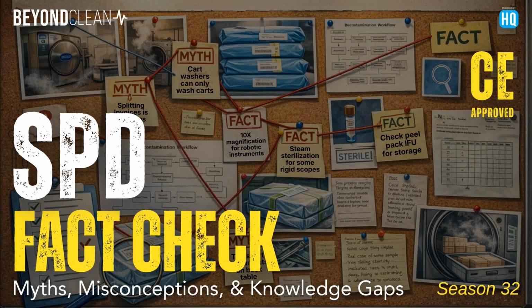From a manufacturing or design standpoint, we're concerned with how quickly we've ramped that temperature up and how quickly we've ramped it down. Let me give you an example: a conventional oven. When we turn it on to heat up, it slowly ramps up to temperature, exposes whatever we're cooking for a chosen period, and then slowly cools down. That gives the optics inside a rigid endoscope the opportunity to expand and contract.